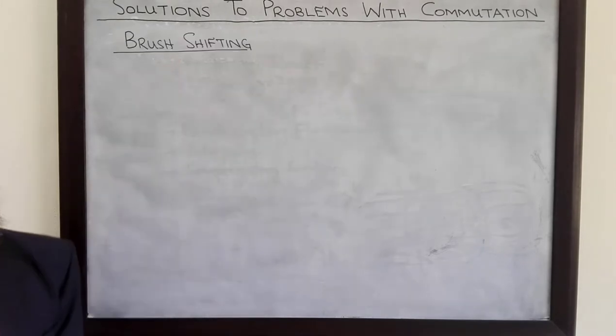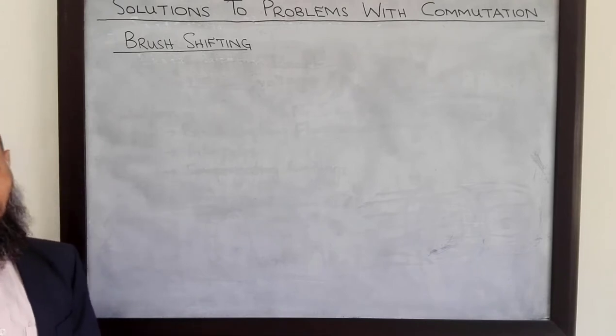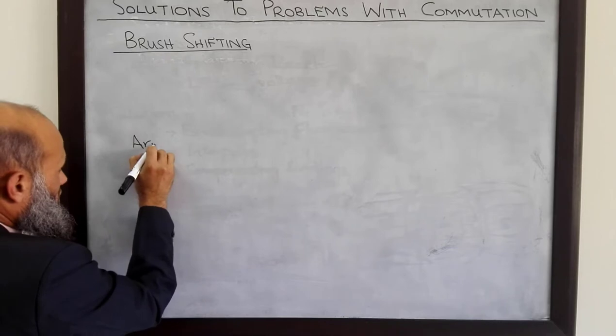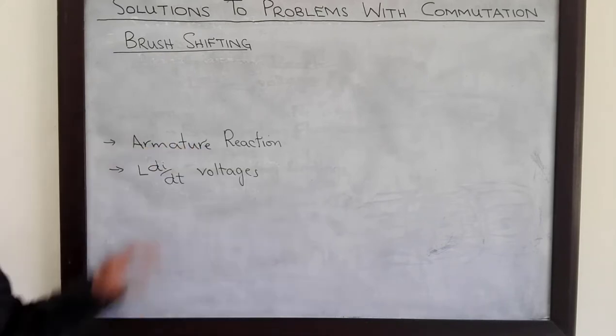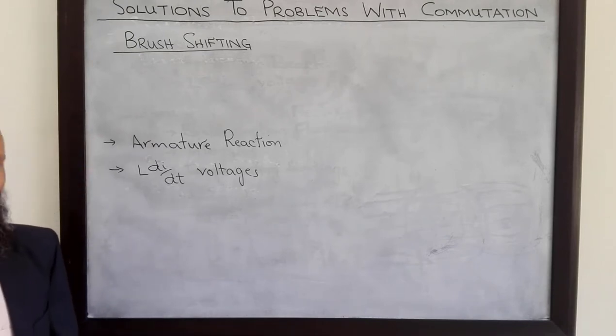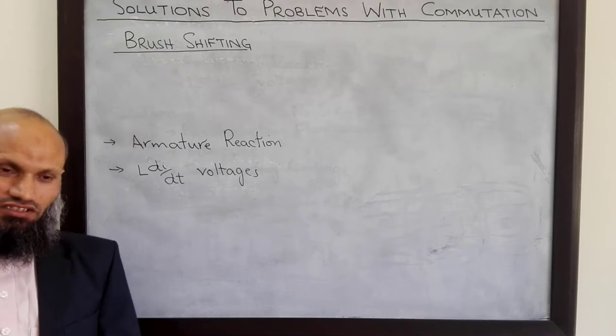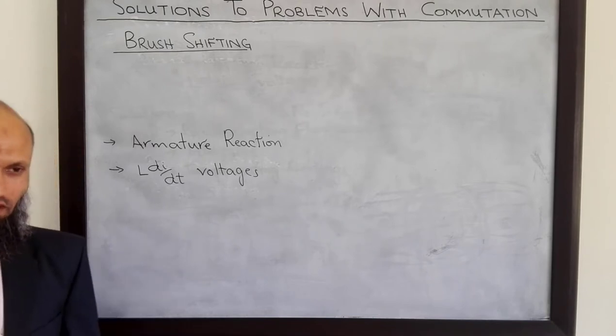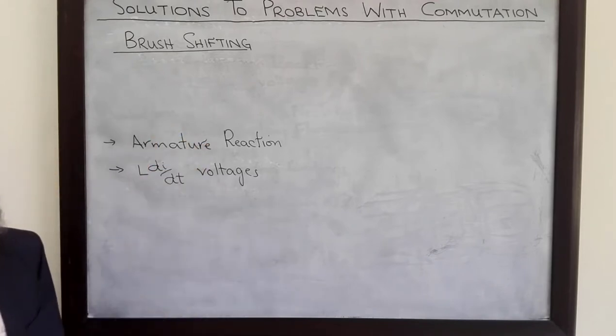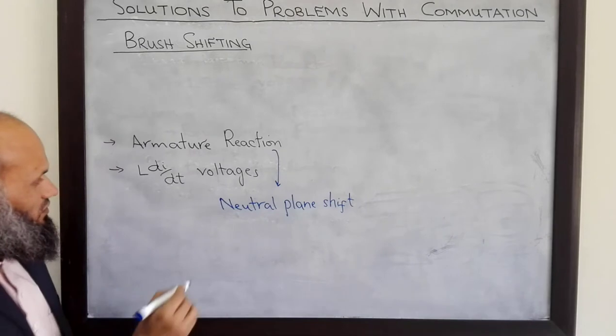In order to discuss these possible solutions, let's first revisit our understanding of the two problems: armature reaction and L di/dt effect. We know that due to current in the coils of the rotor, there is a magnetic field around the coils themselves. That magnetic field interacts with the magnetic field of the main poles and distorts it. That distortion in the MMF is called armature reaction, and it has two consequences: neutral plane shift and flux weakening.